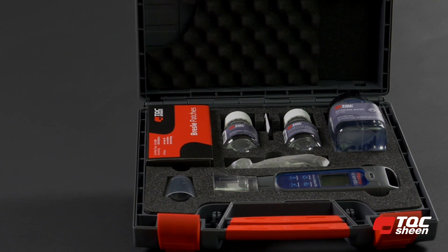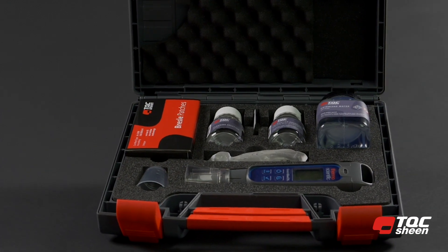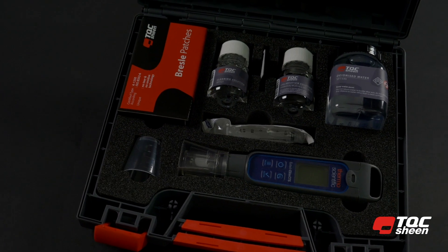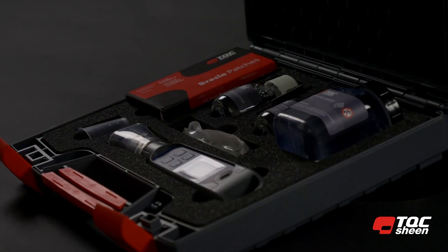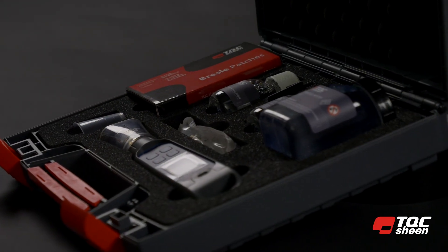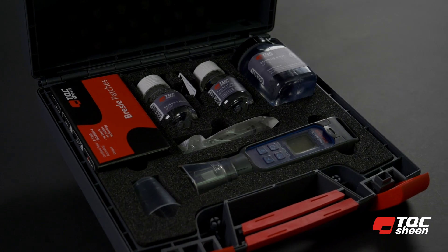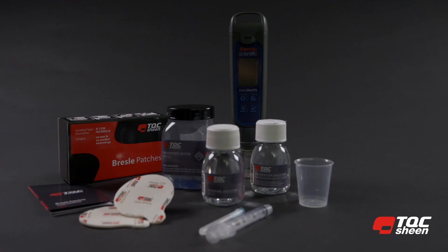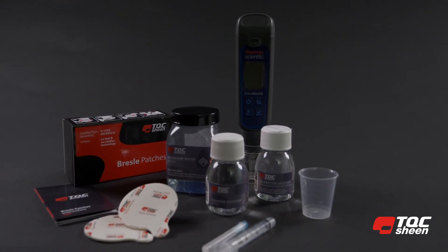What will we measure with the TQC Sheen Bresle Test Kit? It's a user-friendly test kit for determining the amount of water-soluble salts on blasted surfaces prior to the application of coatings. The unique method, according to ISO 8502 part 6 and part 9 standards, immediately shows results in milligrams per square meter soluble salts measured as sodium chloride.